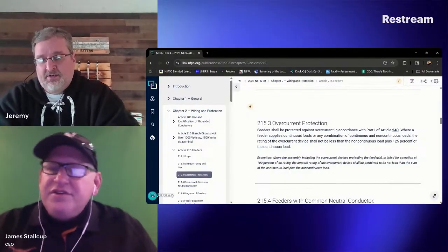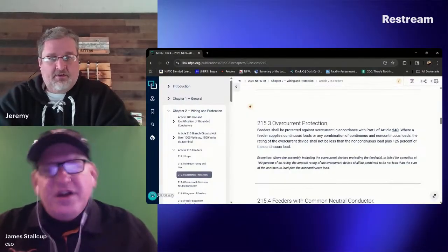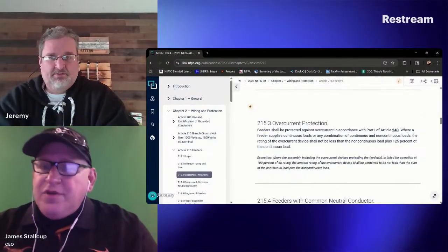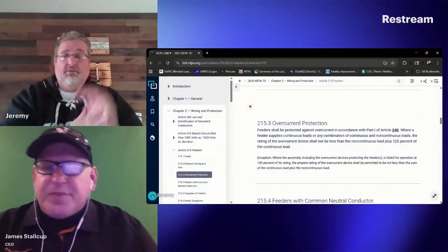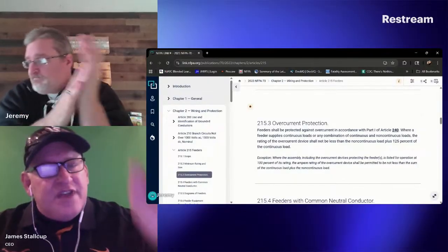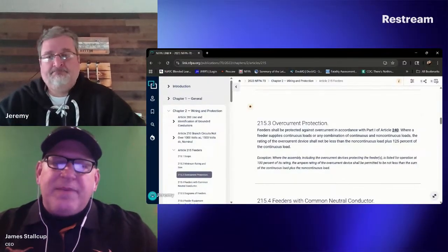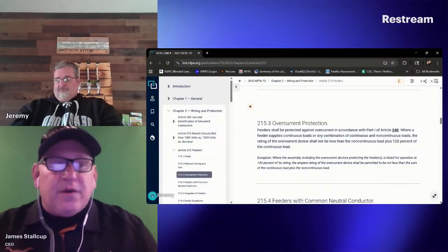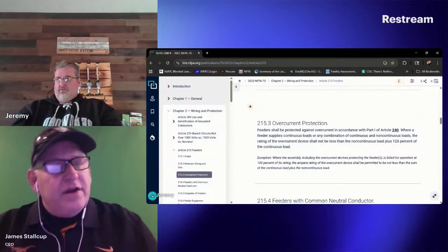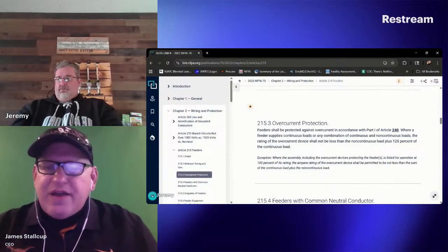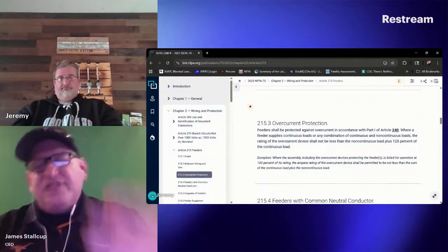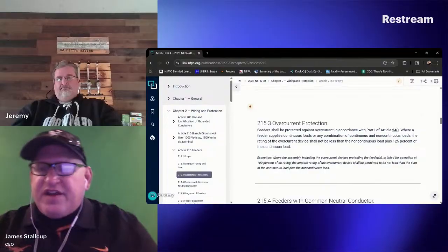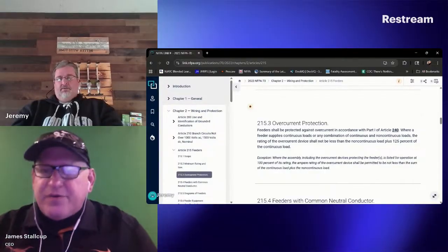Well, see what it says. 240.4, conductors other than flexible cords, flexible cables, and fixture wires. Oh my God. No, I'm looking at 240.4, what it says, protection of conductors. Shall be protected against overcurrent in accordance with the ampacity specified in 310.14 unless otherwise permitted or required. Oh, looky there, 240.4 A through H. So my conductors were sized, and then my overcurrent device is based on what it tells me to do there for the protection of those conductors, and it tells me to go down.